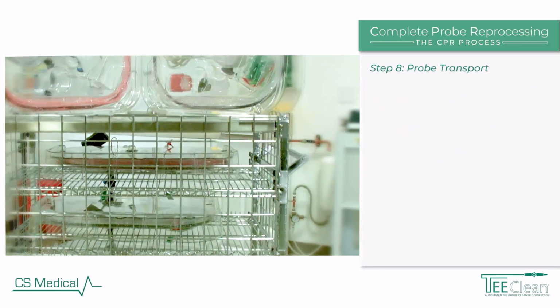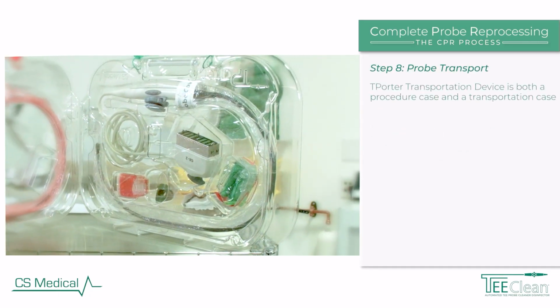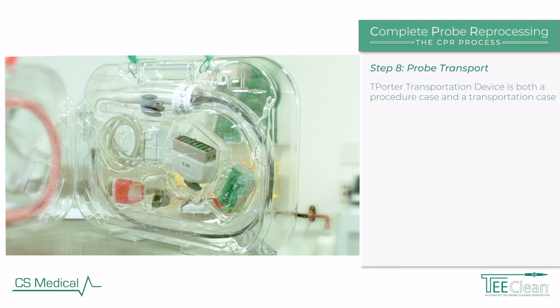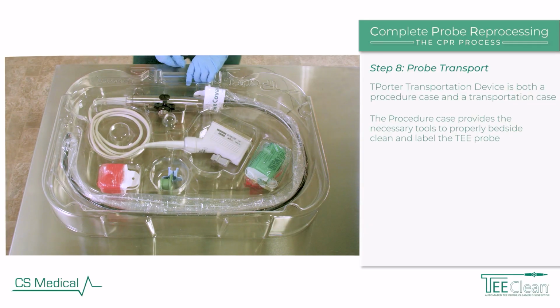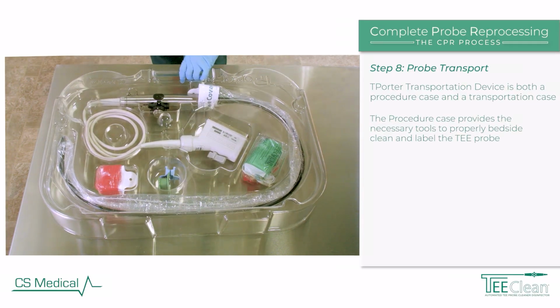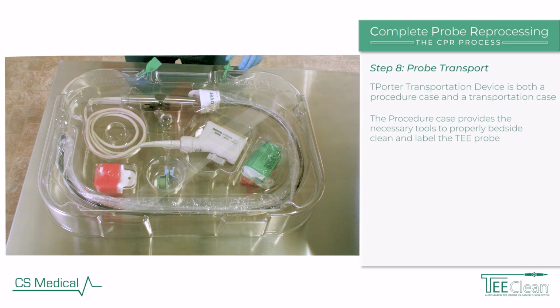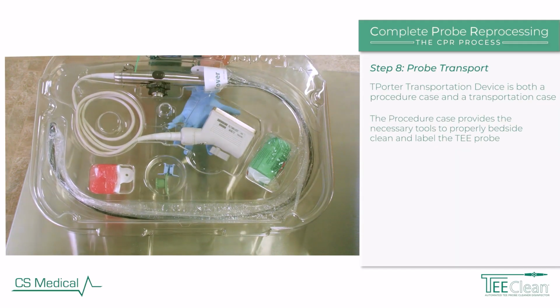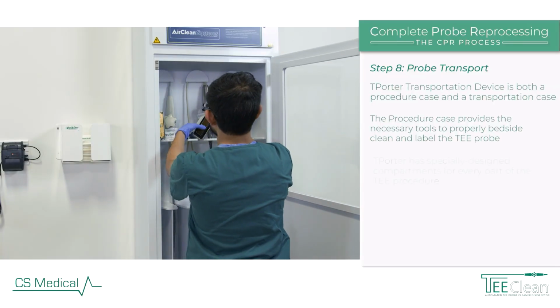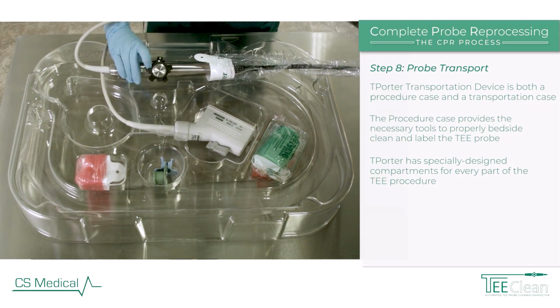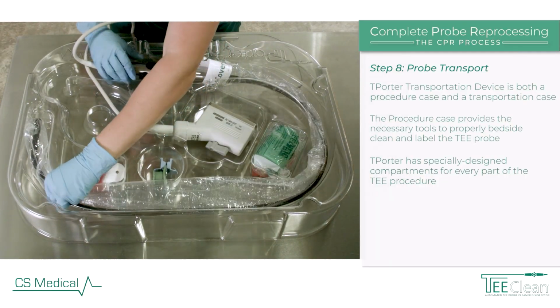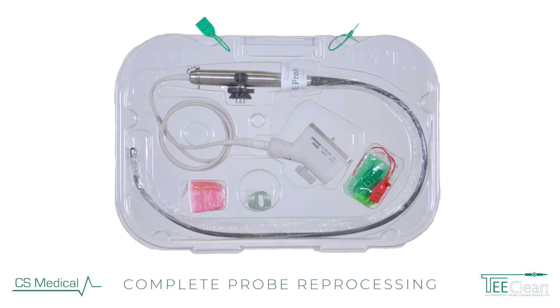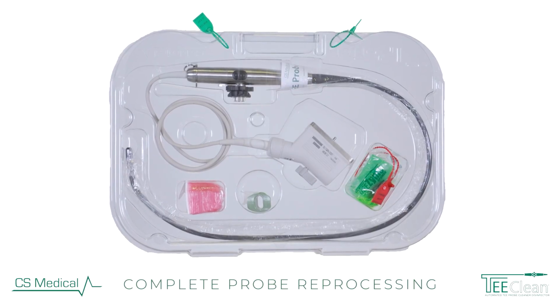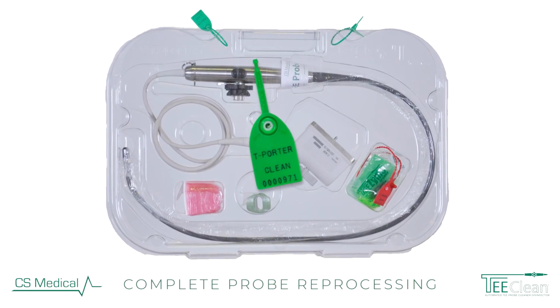Step 8. Probe transport. T-Porter transportation device is both a procedure case and a transportation case for the TEE probe. The procedure case is set up to support the TEE procedure and provide the necessary tools to properly bedside clean and label the TEE probe during transportation. A high-level disinfected TEE probe can be removed from the CleanShield, placed in a plastic pull-up probe cover, and loaded into the T-Porter to allow for safe and secure transportation throughout a healthcare facility. As you can see, T-Porter has specially designed compartments for every part of the TEE procedure. Once loaded into T-Porter, green tie bands labeled "Clean" are used to secure the lid to the case.